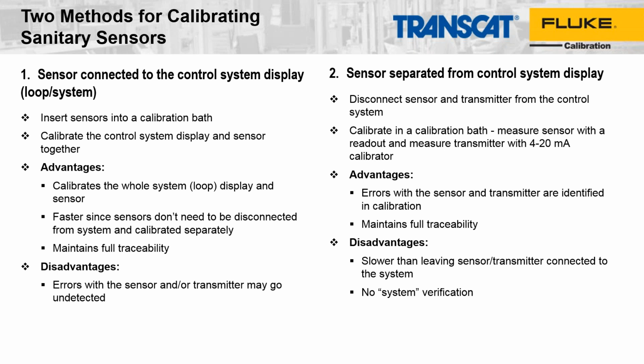Now we have a calibration scenario where the transmitter is calibrated with its own calibration, and then the temperature sensor is calibrated in its own calibration. The advantage here is that we are able to look at both components in this calibration process. We also still maintain full traceability. The disadvantage is that it's a little bit slower to do this because it's two separate cals, and also you have to take the time to disconnect these components from the controller system. And there's also no system verification. We anticipate in this method that once the two components are calibrated, when they come back together, everything will work correctly. But I know some facilities always want to have a little extra warm fuzzy to know that the two components working together is working correctly, as the theory dictates.